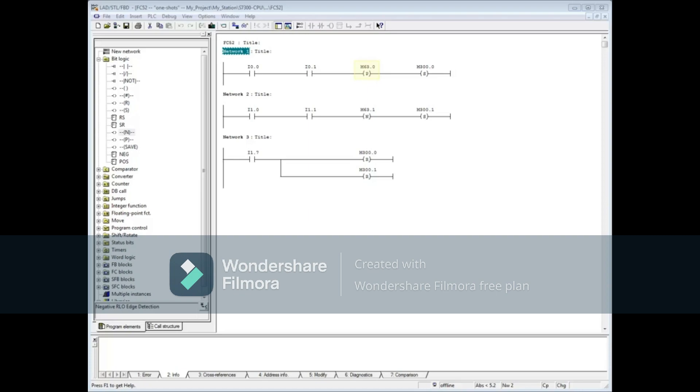Network 1 has a positive edge pulse coil or positive one-shot. Network 2 has a negative edge coil or negative one-shot. Each pulse coil gets assigned a unique memory bit which tracks the incoming logic and determines when a pulse should be fired through to the coil.